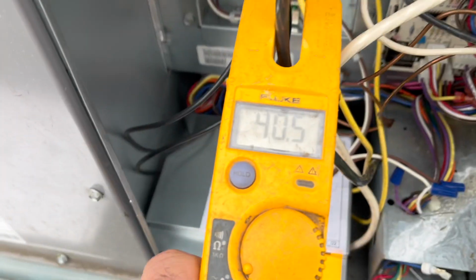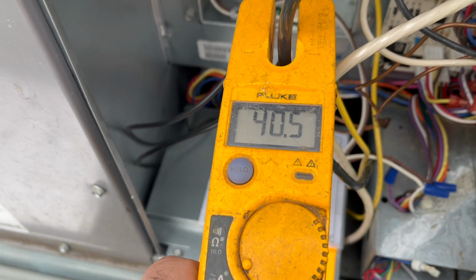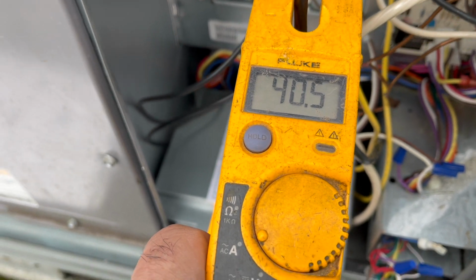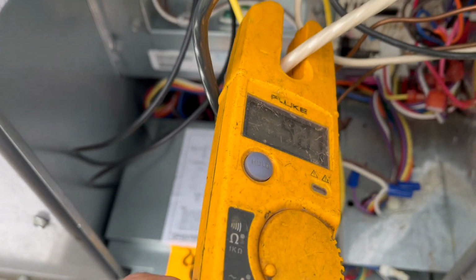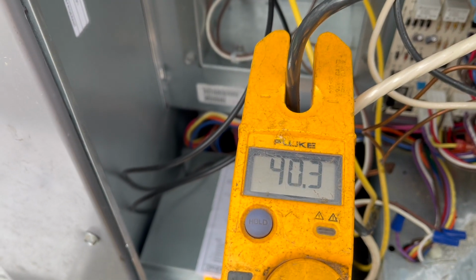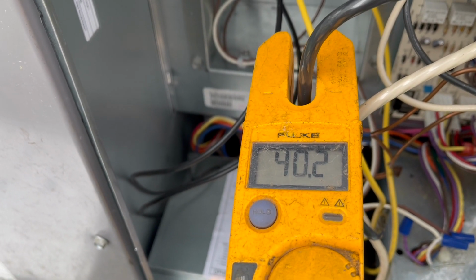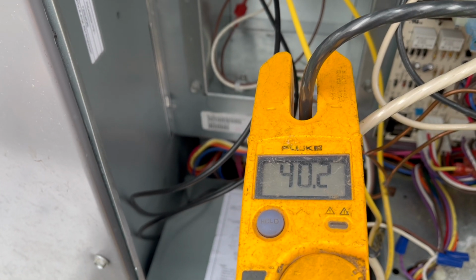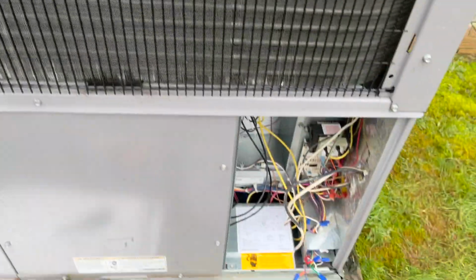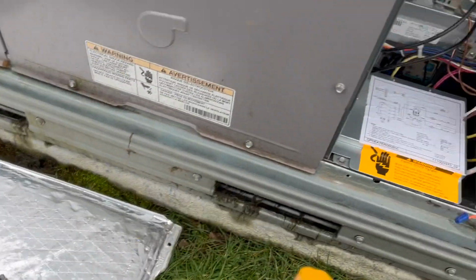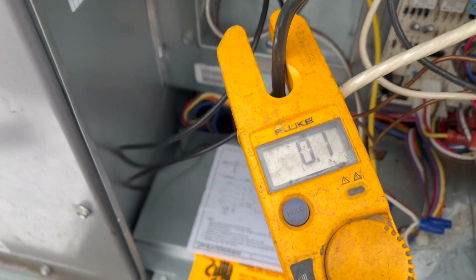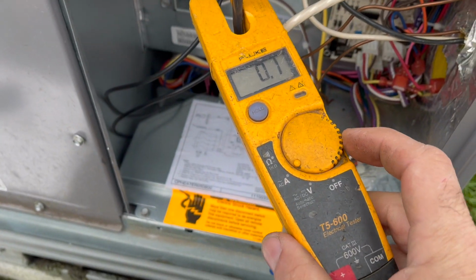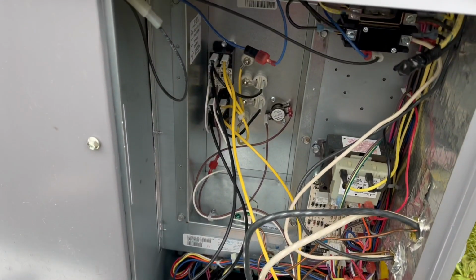Went ahead and flipped the heat breaker on just to confirm that the defrost did have it turned on, and it does. That's the only thing these two number 6s go to is the heat kit there. So we should have around 10 kW of heat going into the house right now as well. And she just switched back out. Just make sure the heat went off.